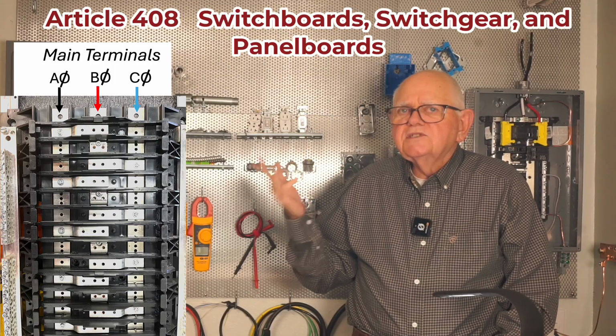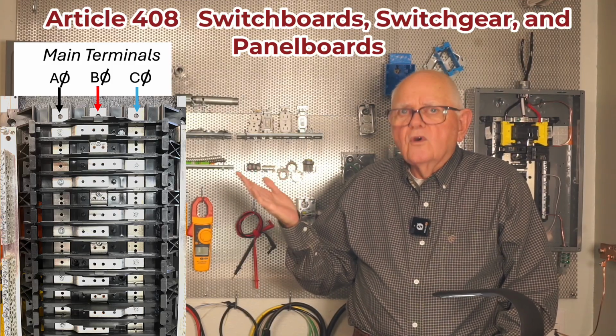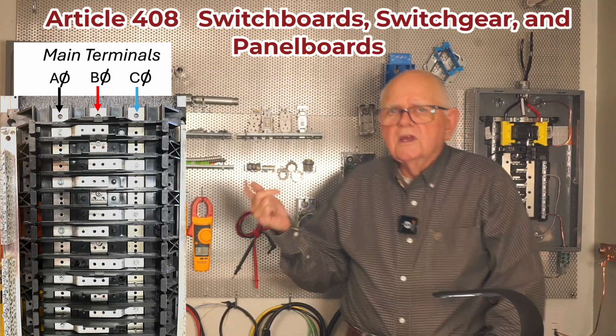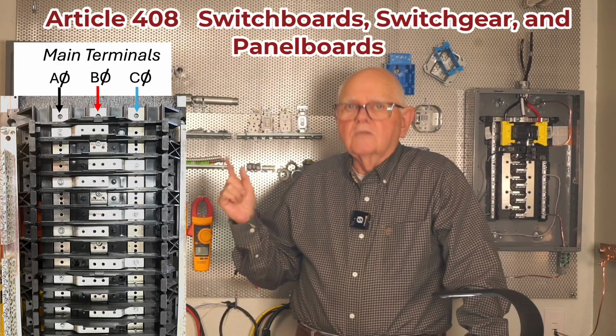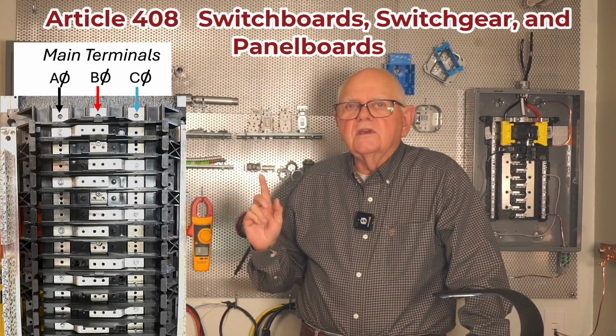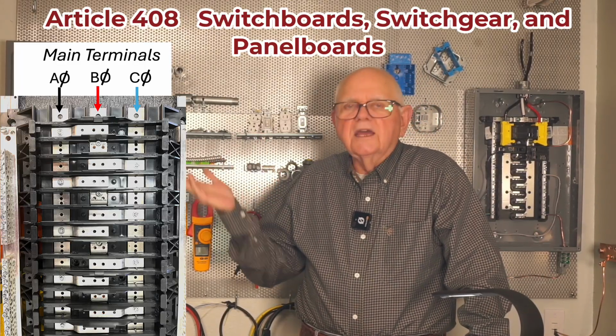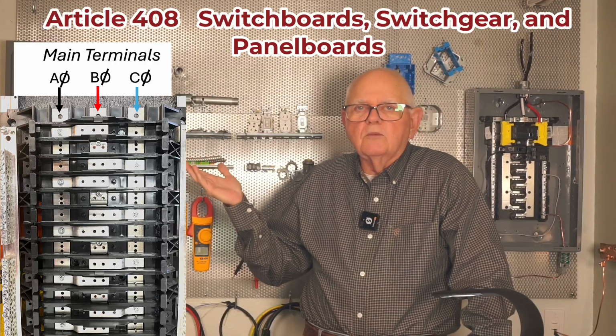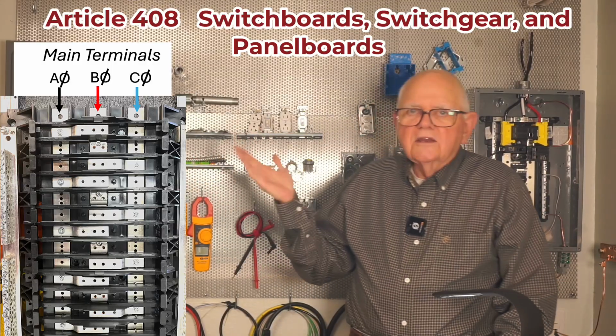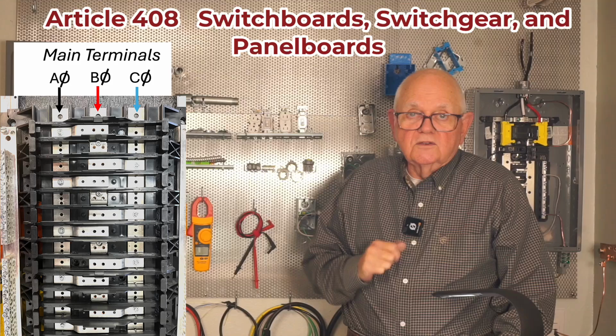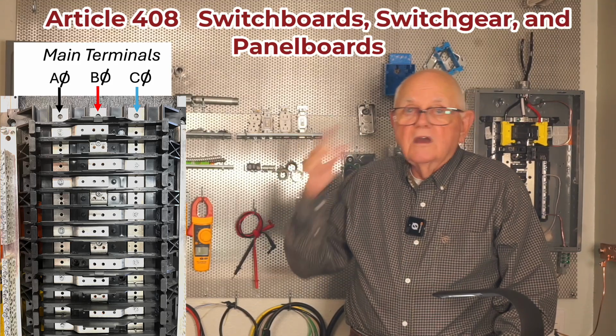So I have 3 separate buses. Article 408 says on the 3-phase panel board, those buses shall be from left to right, phases A, B, and C. And if I'm going to take a high leg, if a delta is supplying this panel board, then the high leg must be phase B as well. Okay, so phase B, orange in color.